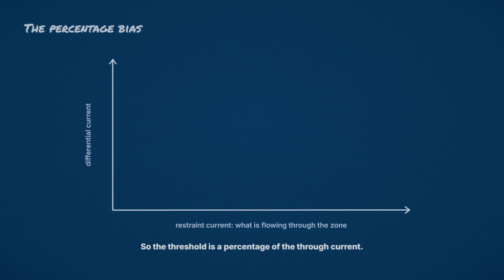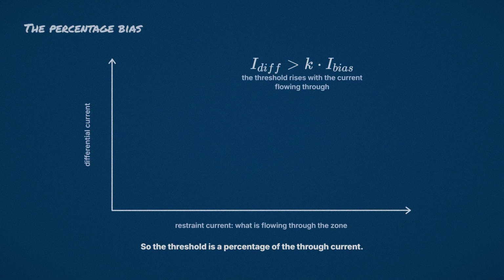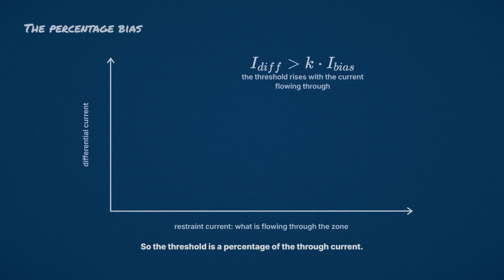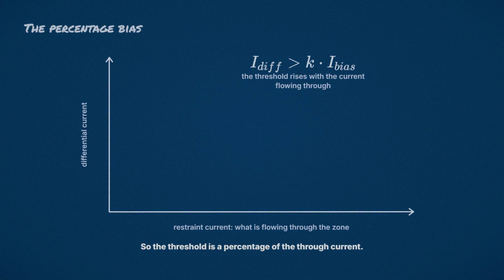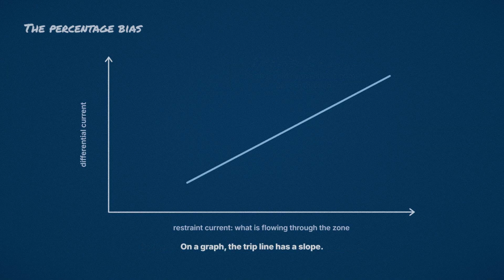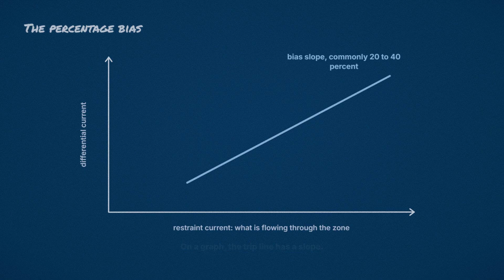So we use a percentage bias, which is also called a restraint. The relay no longer trips on a fixed amount of difference. It needs the differential current to be a certain percentage of the current flowing through the zone. The more current passes through, the more difference the relay will tolerate before it acts. On a graph, the trip line has a slope. A common setting is 20 to 40%. Near the origin, that line is flat at a minimum pickup, so tiny standing differences are ignored.